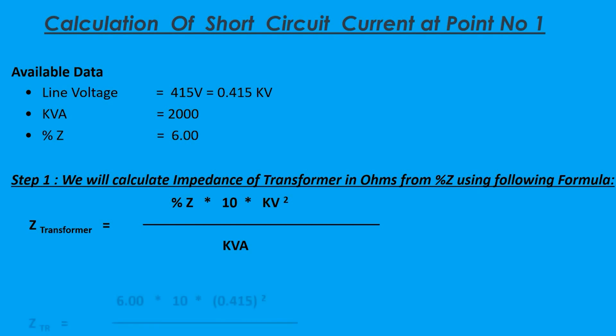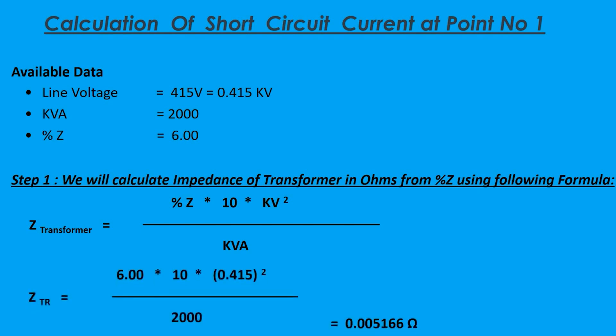Therefore, Z transformer equals 6 times 10 times 0.415 squared, divided by 2000, which comes to 0.005166 ohms.